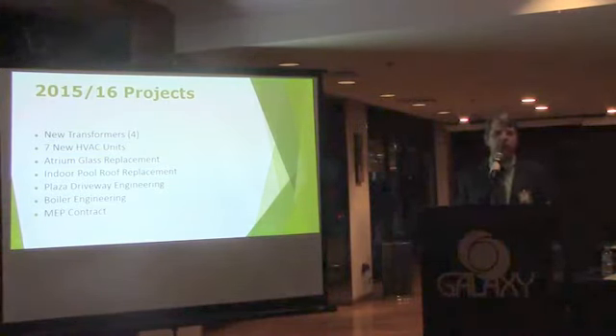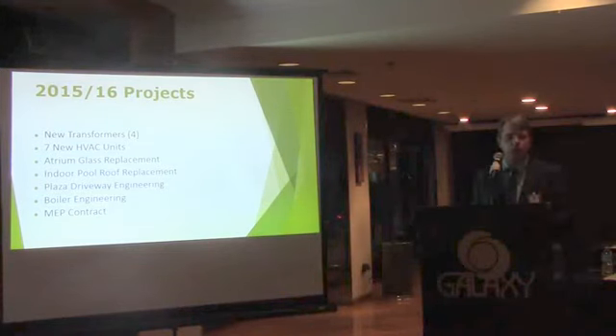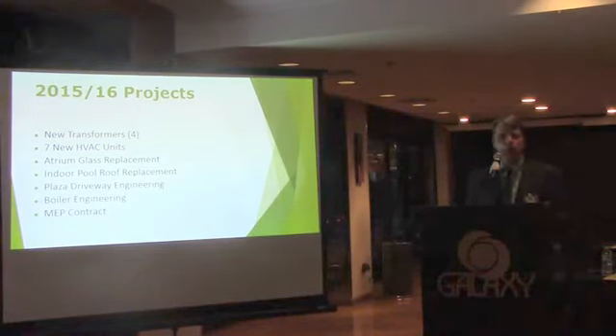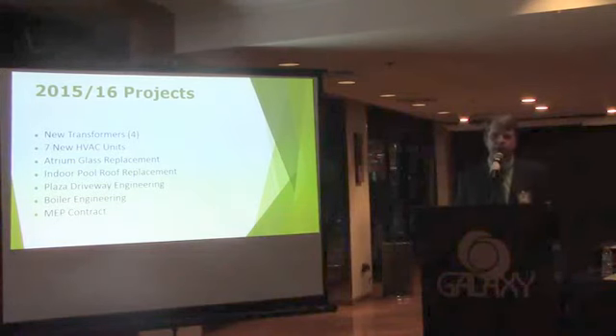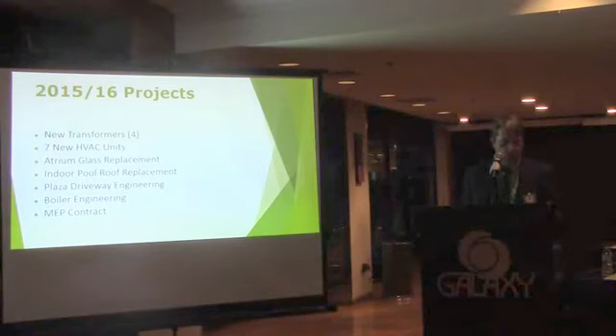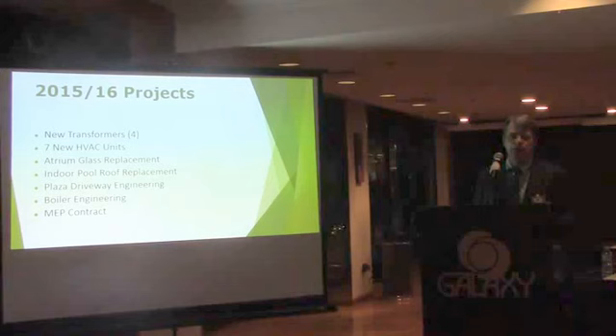Some of this equipment is rather large. The 500 kVA has the potential of powering up several hundred homes. So loss of some of these transformers would have significantly impacted several homeowners. These transformers are original to the building, in excess of 45 years old. The phases are load imbalanced, they're humming, they're overheating, they're energy inefficient, and they're near time for failure. So the association took the effort to replace 4 of those last year. We are projected to continue those inspections this year and carry that replacement schedule forward a little further.